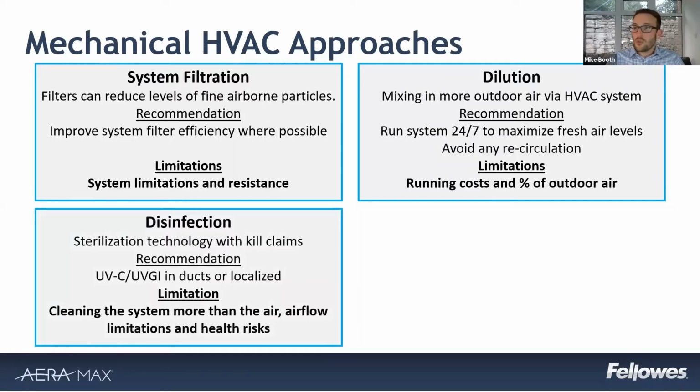Disinfection is the use of some form of sterilization technology introduced within the system. The most commonly accepted ones are things like UVC or UVGI. You might be familiar with both of those terms. Really, the issue here is that depending on how these technologies are introduced, they can actually spend more time cleaning the inside of the system than they can actually benefit in the air. It is quite an exact science in order to get a UV solution right.